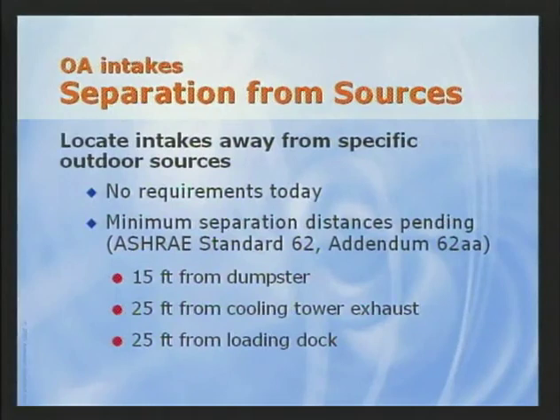I suspect most designers just consider it good practice or common sense to locate outdoor air intakes away from strong contaminant sources. Historically, neither Standard 62 nor other guidelines specifically address the separation issue. Be advised that Addenda 62AA, currently in the review process of Standard 62, will specify the minimum distances that sources such as dumpsters, cooling towers, and loading docks must be away from outdoor intakes. Although not yet final, some of the proposed distances are 15 feet for dumpsters and 25 feet for cooling towers and loading docks. This will probably not be a big deal for most projects, but it is something you should be aware of.